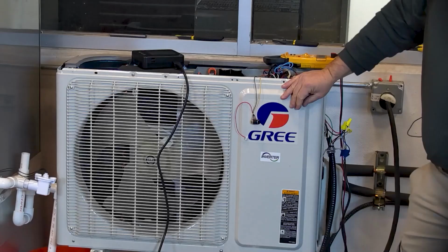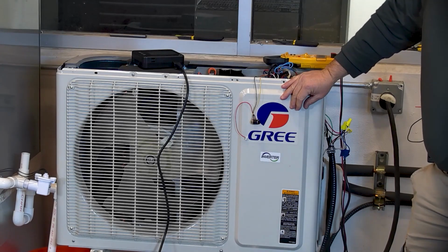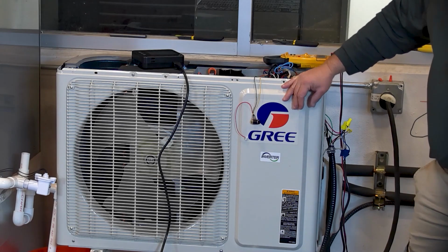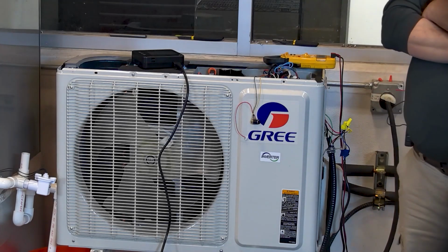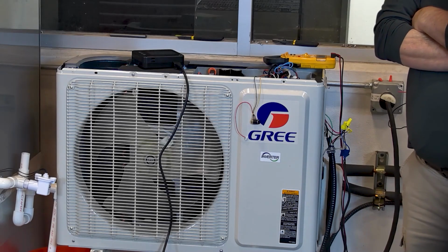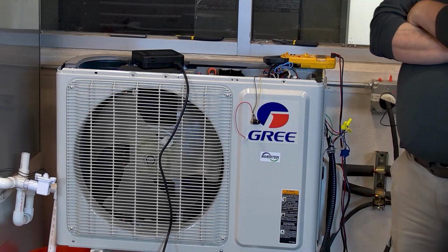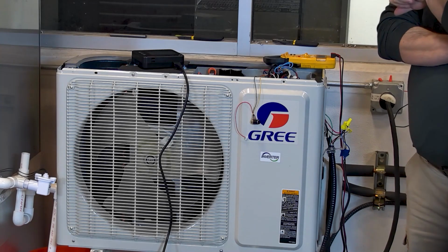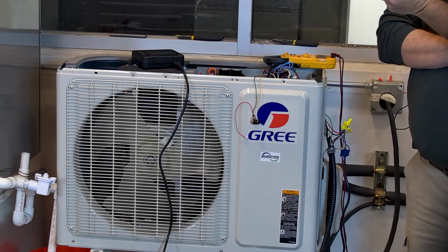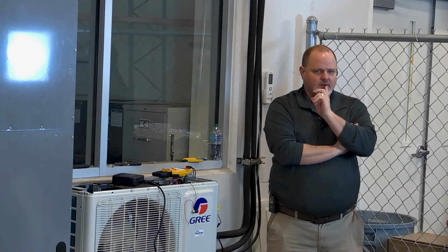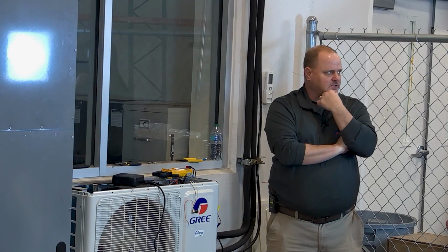We started out like this, guys, so that we can demonstrate shoving it into a high discharge temp code. So obviously we're not going to come out here and let refrigerant out to cause that to do it. So we put a rheostat on it just so we can play around with the discharge temperature and actually show what happens when you get the discharge temperature too high. So we're trying to simulate error codes as best we can for the conditions that we have to be able to show you guys. So with that said, we set it up like this so that we can show you that real quick. Then we're going to power the machine down and we're going to demonstrate simulating the indoor unit and simulating the outdoor unit so that you guys can see how well this tool works for E6 communication troubleshooting.